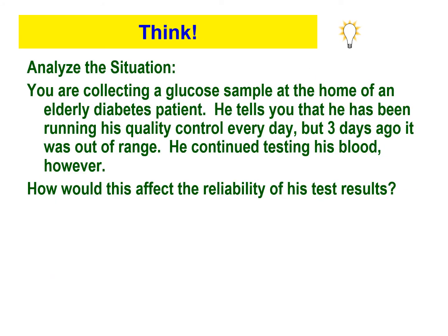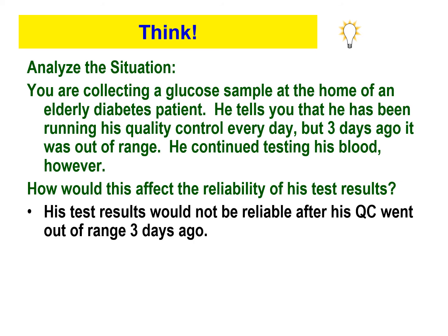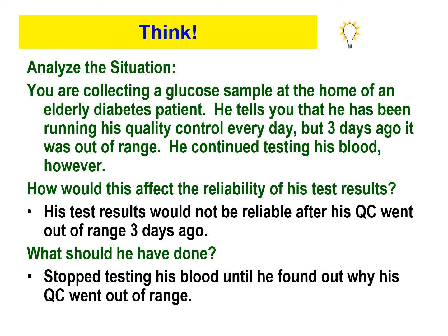So here's one of our thinking situations, right? I want y'all to read over this, analyze this situation, think it through thoroughly, use your thinking cap, okay? And then pause it now and see if you're getting the right answer. Remember, you stop using that instrument. Do not test your patients on it until you can get your QC to come in range and you figure out what's going on.